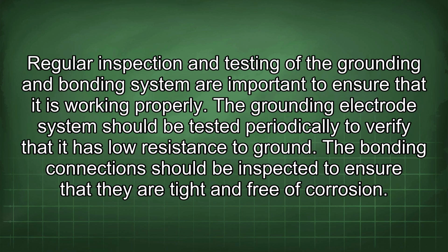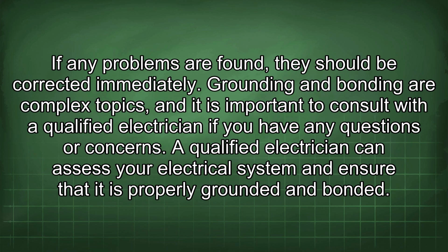Regular inspection and testing of the grounding and bonding system are important to ensure that it is working properly. The grounding electrode system should be tested periodically to verify that it has low resistance to ground. The bonding connections should be inspected to ensure that they are tight and free of corrosion. If any problems are found, they should be corrected immediately.